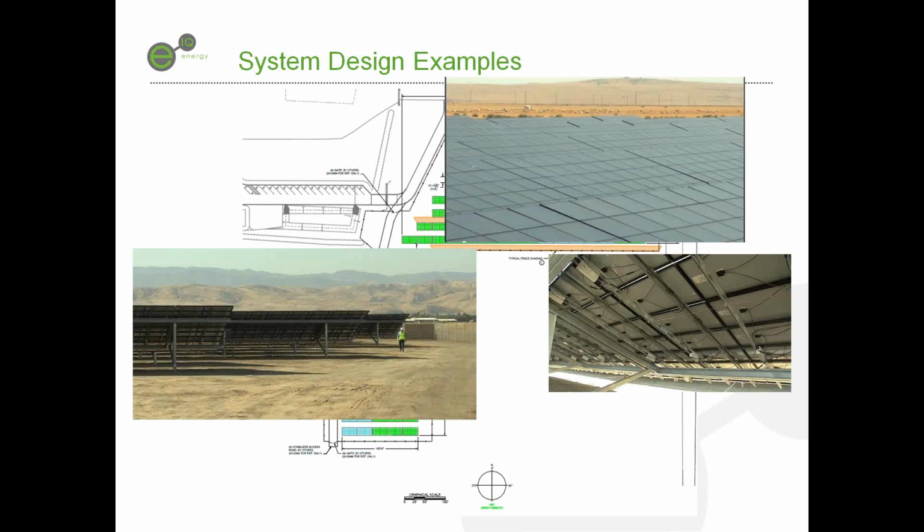So if you kind of take a look at what this site looked like as it installed, you can see here the vBoost units that were mounted underneath the modules. And you can see how there was a simple elegance to how they were architected into the solution. There's just basically one vBoost on every other cross member going down here. There's one set high, one set low, and then the modules are actually grouped. We had 4 modules going into each one of these vBoost units here.